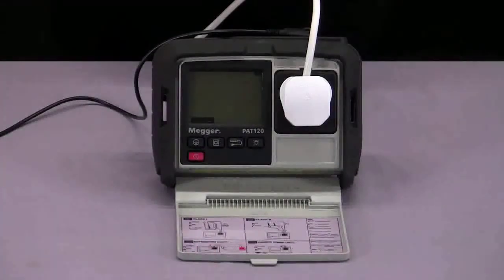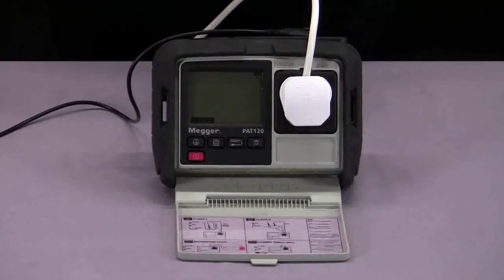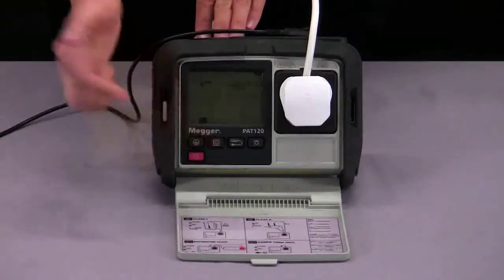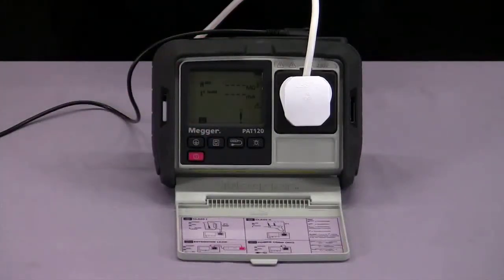For testing Class 2 equipment, again I have my appliance plugged in with my lead connected to any exposed metalwork. I can press my Class 2 button to begin the test. It will start by doing an insulation resistance test at 500 volts, which can be dropped to 250 volts for sensitive equipment. It will then do a substitute leakage test, and my overall pass or fail will be displayed by a tick or a cross in the bottom right hand corner.